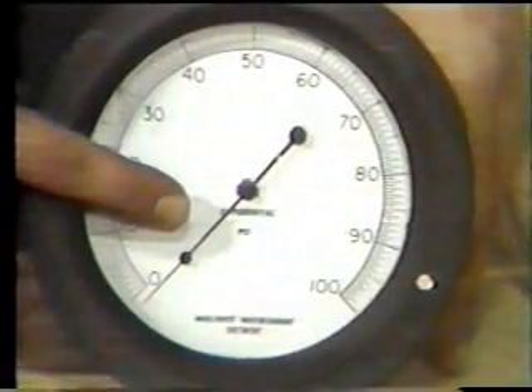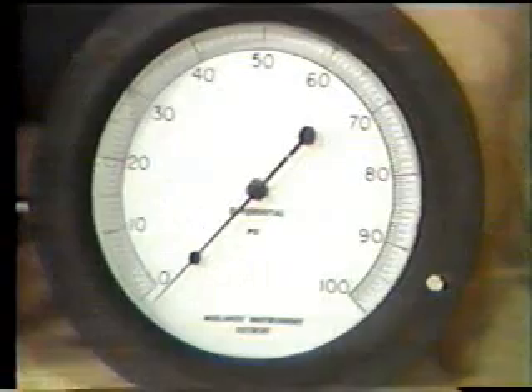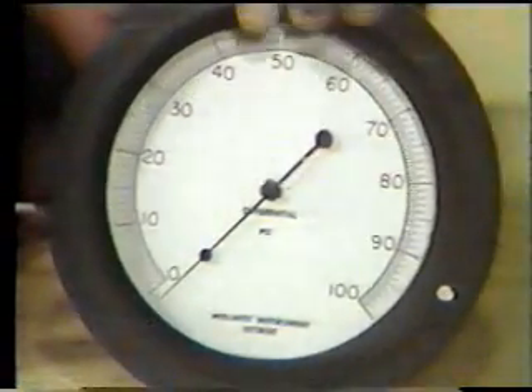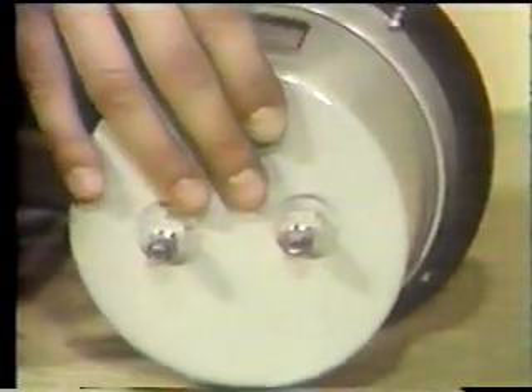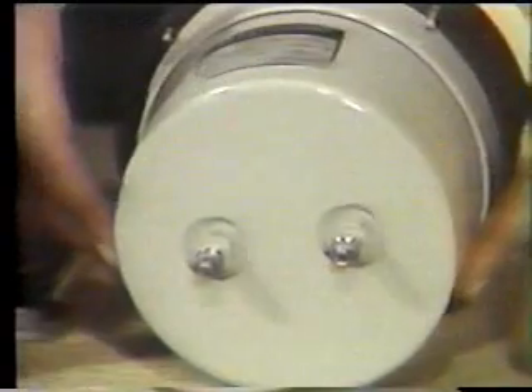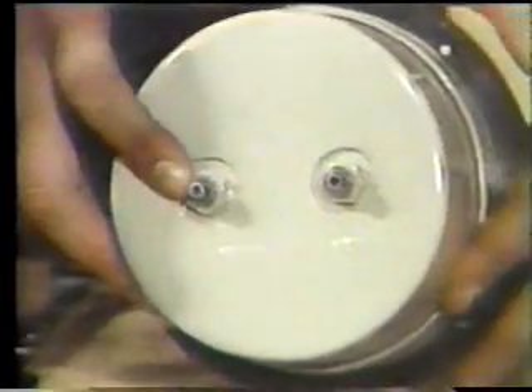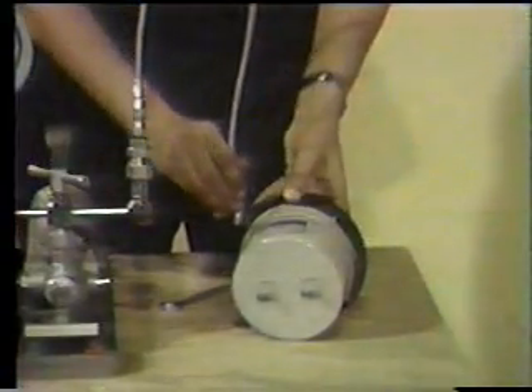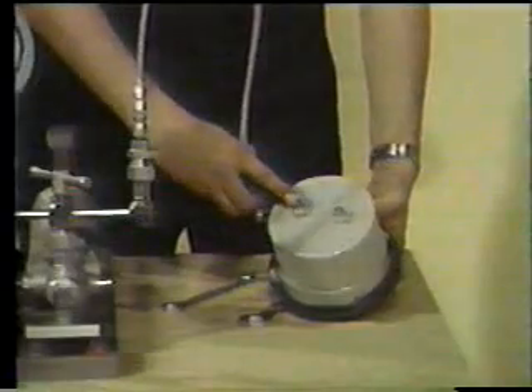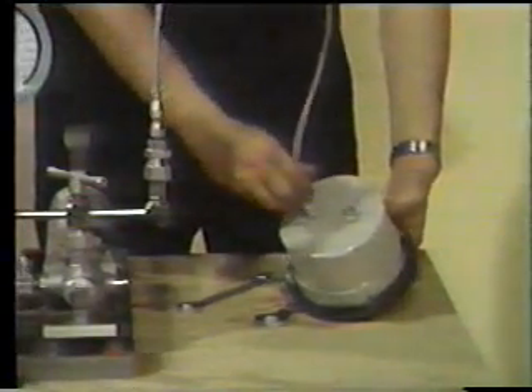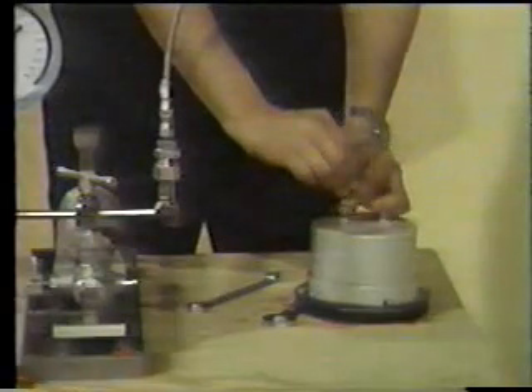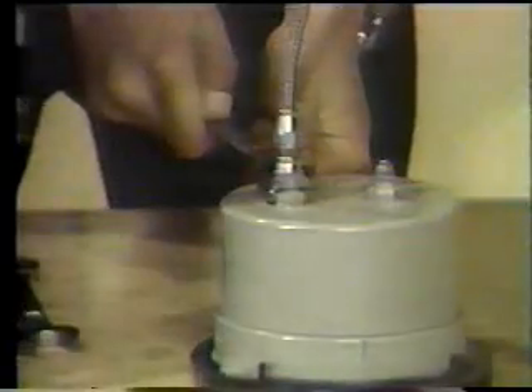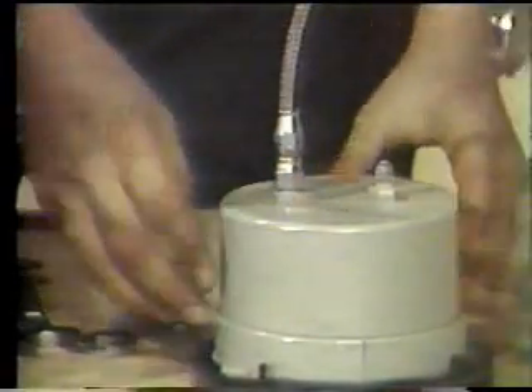Using the same test equipment, you will be able to calibrate a differential pressure gauge, sometimes referred to as a delta P gauge. Note, there are two test connections on the back of the delta P gauge. These connections are labeled high and low. First, connect a line from the pressure source to the connection marked high on the delta P gauge. Be sure to tighten all fittings prior to applying pressure. Once the fittings have been tightened, check to be sure the low side of the gauge is vented to atmosphere.